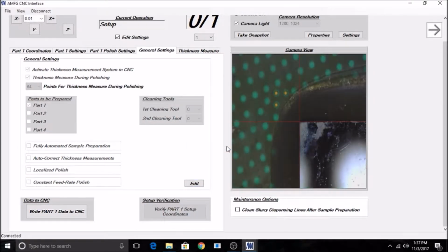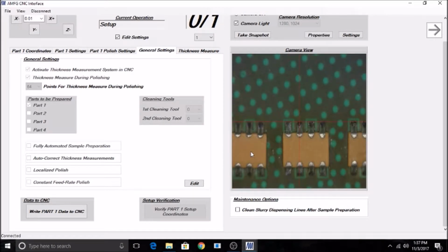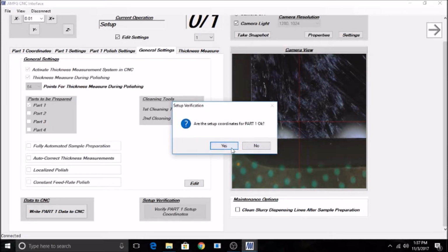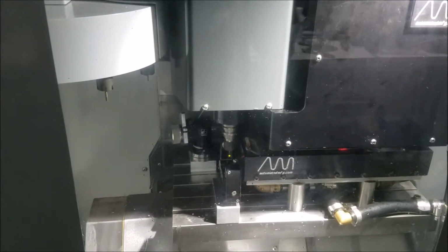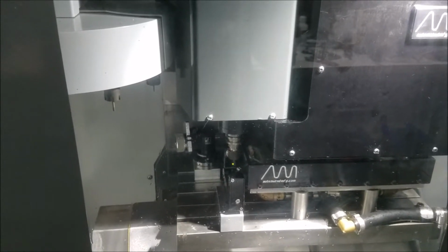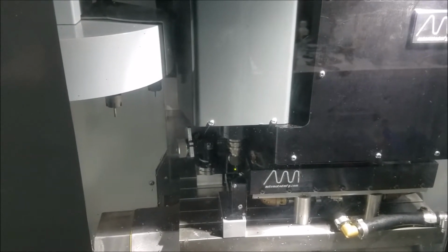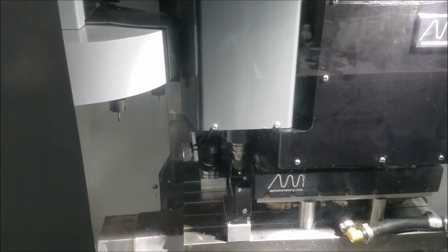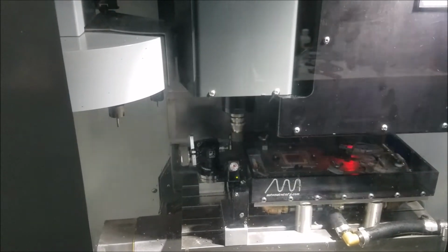We are verifying the different coordinates, boundary conditions, and the location at which we wish to probe. The system uses two different types of tool setters, a laser for our spring-loaded polishing tools, and a contact tool setter for the solid tools. There is also a safety pad check, which makes sure that a polishing pad is present on the polishing tools.